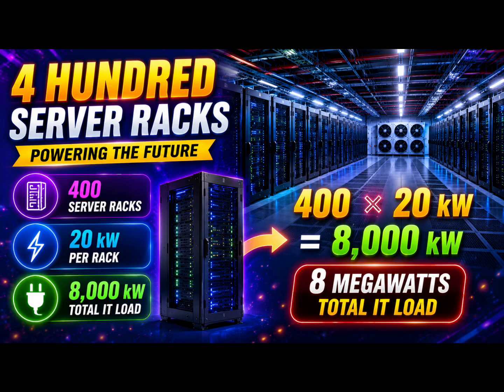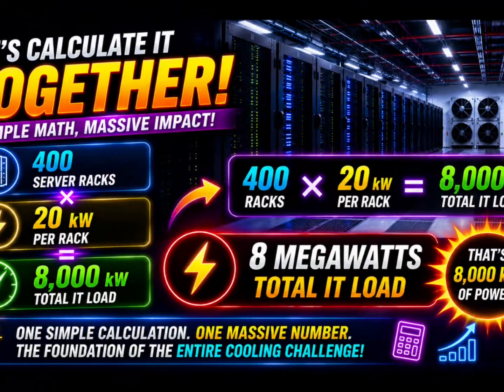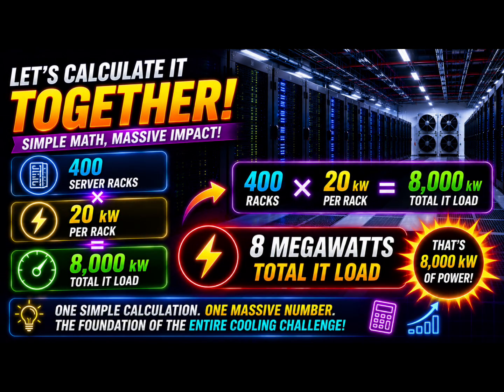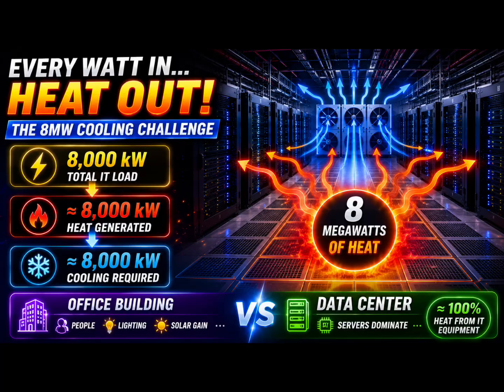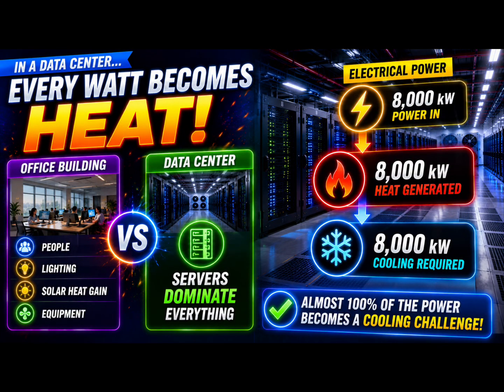At first, 20 kilowatts may not sound extraordinary, but when you multiply that figure by 400 racks, the numbers become astonishing. Let's calculate it together. 400 multiplied by 20 equals 8,000 kilowatts, or simply 8 megawatts. That is our total IT load. And here's something remarkable. That single calculation already represents almost the entire cooling challenge inside the data hall. Because unlike an office building, where cooling must account for people, lighting, and solar heat gain, a data center's different. Here, the servers dominate everything.